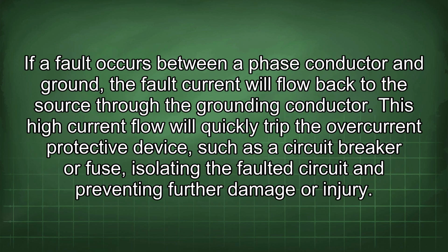If a fault occurs between a phase conductor and ground, the fault current will flow back to the source through the grounding conductor. This high current flow will quickly trip the overcurrent protective device, such as a circuit breaker or fuse, isolating the faulted circuit and preventing further damage or injury.